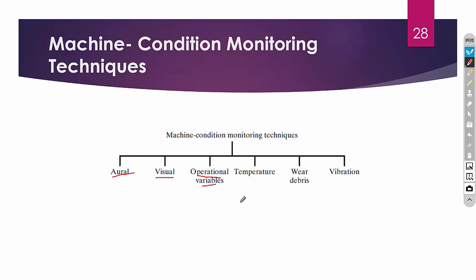Operational variable monitoring includes pressure — in boilers, pressure is monitored continuously, and if it exceeds some limit we can identify a problem. Temperature is also monitored, mostly in power plants. Wear debris analysis is another technique: in journal bearings, lubricants are used between the journal and bearing. If you analyze the lubricant and find small particles of the journal material, it means the bearing is not working properly — friction is high and the journal or lubricant needs to be replaced.